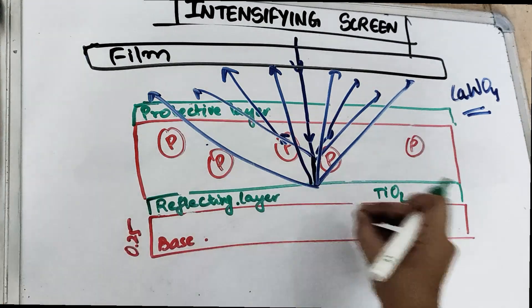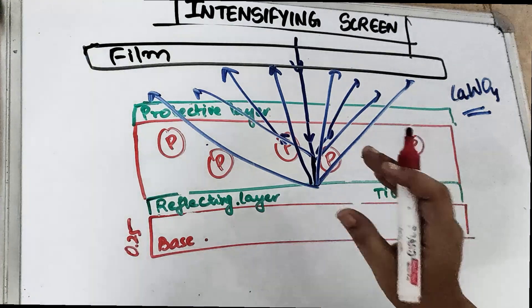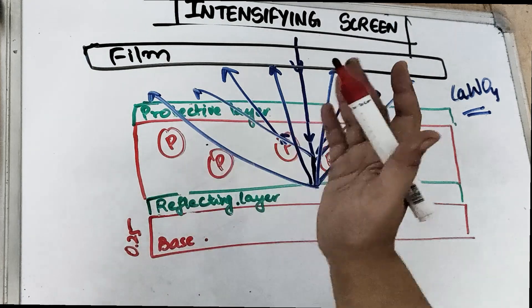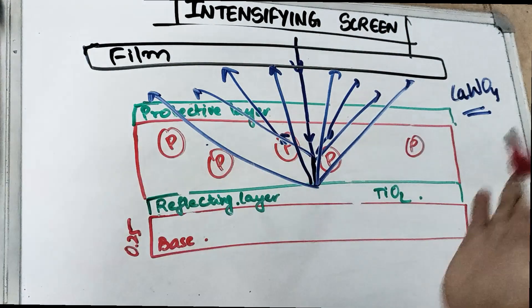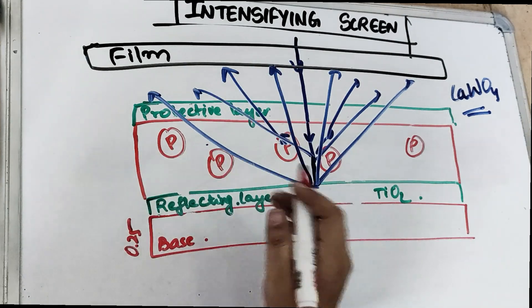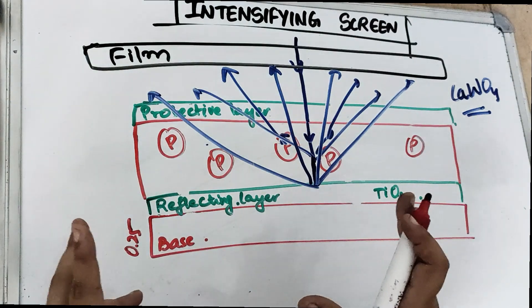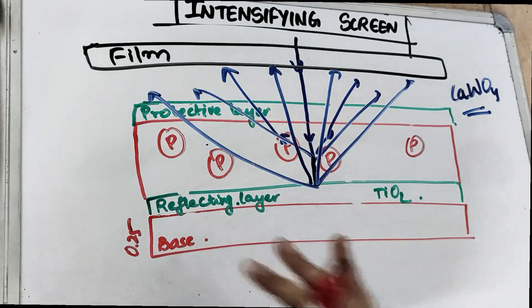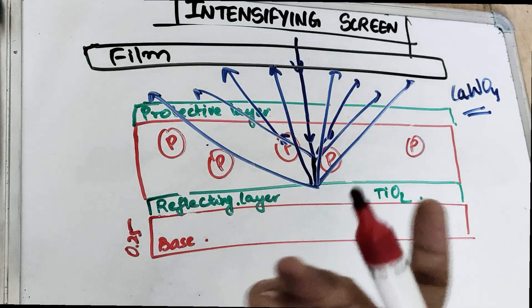The reflecting layer is a very thin layer of titanium dioxide. As we increase the crystal size, the speed of the screen increases. The reflecting layer directs all the light coming — it reflects it back, which increases the sensitivity of the film. But there is a disadvantage: it reduces the sharpness of the image. The clarity of the image is reduced because of this reflecting layer.